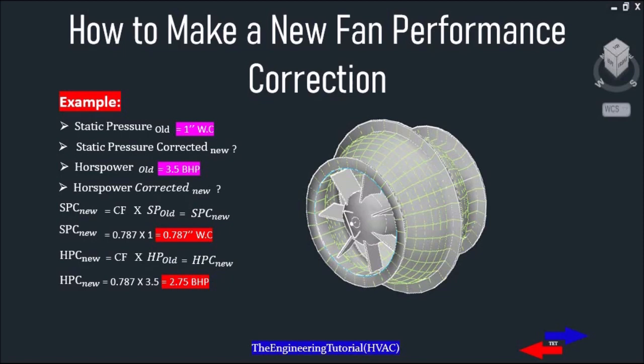Therefore, as altitude and temperature go up, air density changes: the static pressure decreases from 1 to 0.787 inches of water column, and the horsepower changes from 3.5 to 2.75 after increasing altitude and temperature. That's it for today — I appreciate you for watching this video.